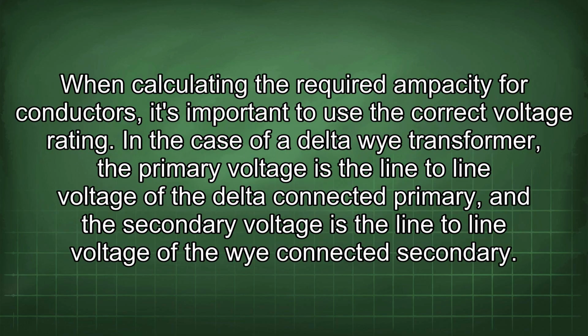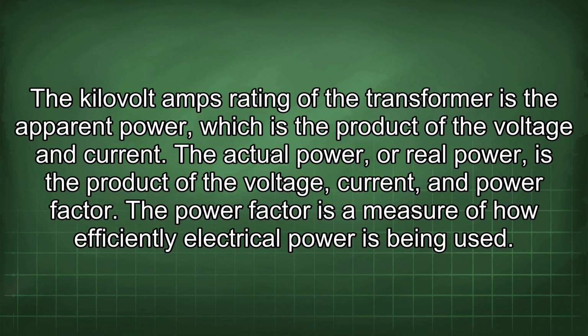When calculating the required ampacity for conductors, it's important to use the correct voltage rating. In the case of a delta-Y transformer, the primary voltage is the line-to-line voltage of the delta-connected primary, and the secondary voltage is the line-to-line voltage of the Y-connected secondary. The kilovolt amps rating of the transformer is the apparent power, which is the product of the voltage and current. The actual power, or real power, is the product of the voltage, current, and power factor. The power factor is a measure of how efficiently electrical power is being used.